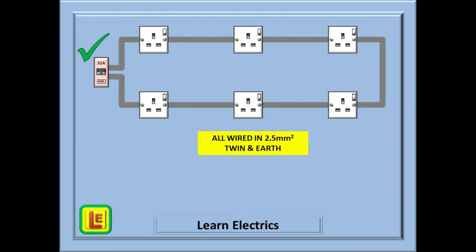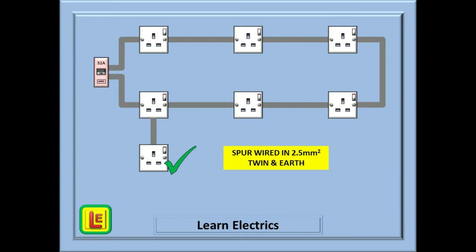A ring circuit does not have to be protected by a 32 amp breaker, but whatever the size is we need to follow the same rules to prevent overloading of any of the cables. Here we have added a single socket as a spur from the ring and we have used 2.5mm cable for the connection to the ring.